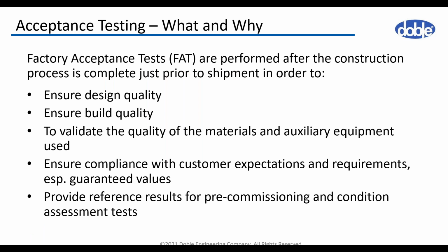FATs are performed once the construction process is complete and the active part is positioned into the tank. The purpose is to reveal any design and manufacturing defects and to verify the materials used. It is the first time we can see the unit assembled and check the functionality of the auxiliary equipment. From the customer's point of view, it is faster and much more cost-effective to rectify any errors at the factory rather than on site. The works tests will ensure the transformer complies with our expectations and meets the guaranteed limits. In addition, FATs provide valuable reference data for subsequent condition assessment testing in service and after commissioning.